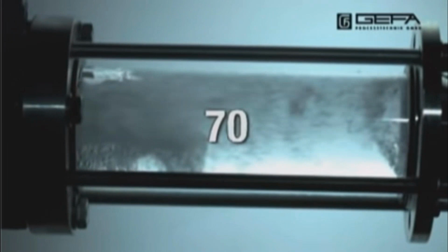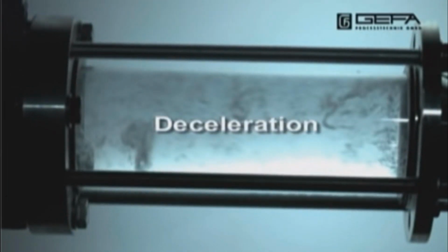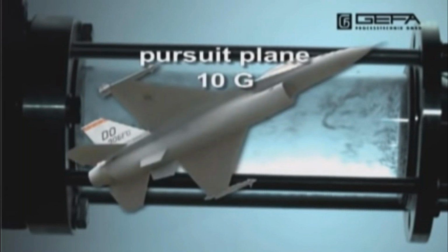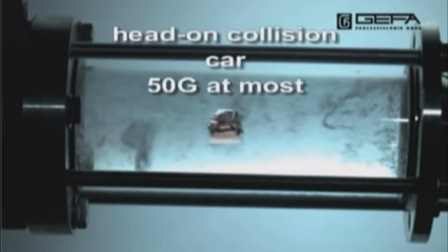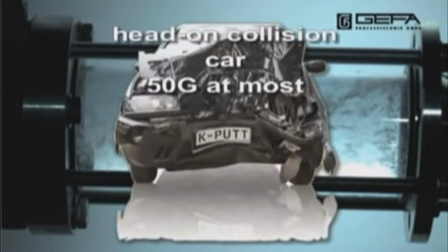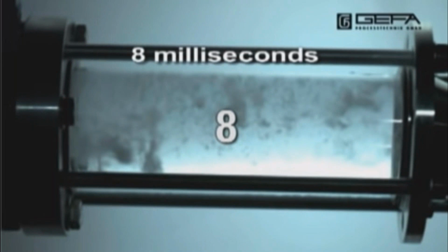Now steam bubbles are decomposed and deceleration begins. For comparison, a pursuit plane reaches 10 G at most. In an accident, deceleration is 50 G at most. Within 8 milliseconds, the speed of the water is dropping to zero. In this time, you cannot see any vacuum bubbles.